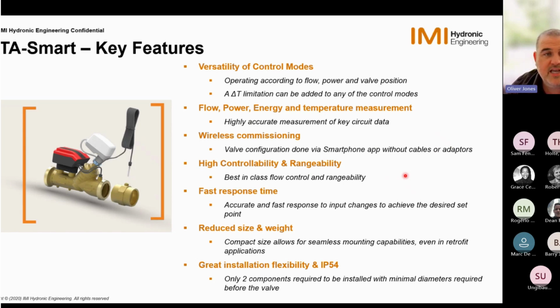So a high controllability and rangeability. So it's best in class for flow control and rangeability. So that means we can control down very low, and I'll show you why that's important shortly. Fast response time. So obviously, as we saw over the sub-control loops, we are now able to make those system changes very quickly over that sub-control loop, because we are constantly monitoring the flow, the temperature, the power output, and we get ultimately a fast response time.